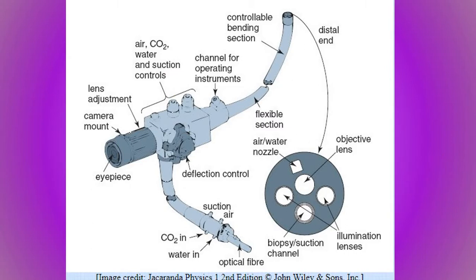Endoscopes are a simple design in practice, but the theory behind it contains many physical and mechanical qualities that make it an incredibly effective tool for minimally invasive surgery. The main body of the endoscope contains the air, CO2, water and suction controls, as well as the deflection control. Leading off the main body towards the viewer is the main camera mount. This contains an eyepiece and lens adjustment for ultimate adjustability. On the other end is a small hole that leads into a channel for operating instruments.